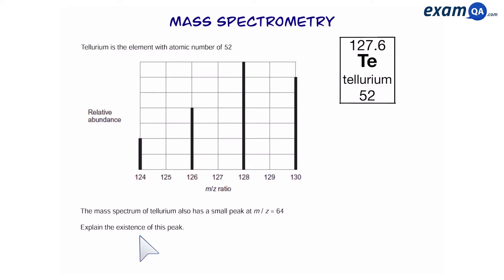So to answer that let's first have a look at this. This peak was caused by an atom of Tellurium with a mass of 124 and a charge of plus one. When we do mass divided by charge that's going to give us 124. So that's why we have the m/z value of 124.